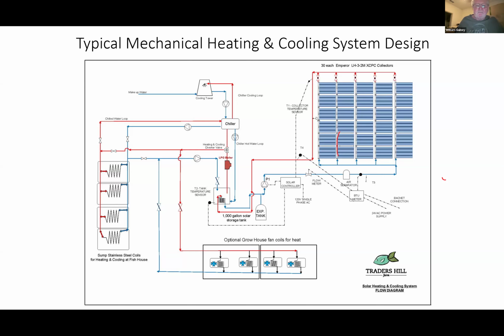In this case, we had both a heating system and a chiller. So the chiller would provide the cooling of the fish house when necessary. In the winter, it's awful, because of the temperature differential, you basically walk into a fish house and it's raining from the roof. All the evaporation is condensing on the roof, dripping back into the room. So solar thermal can provide a solution for that.